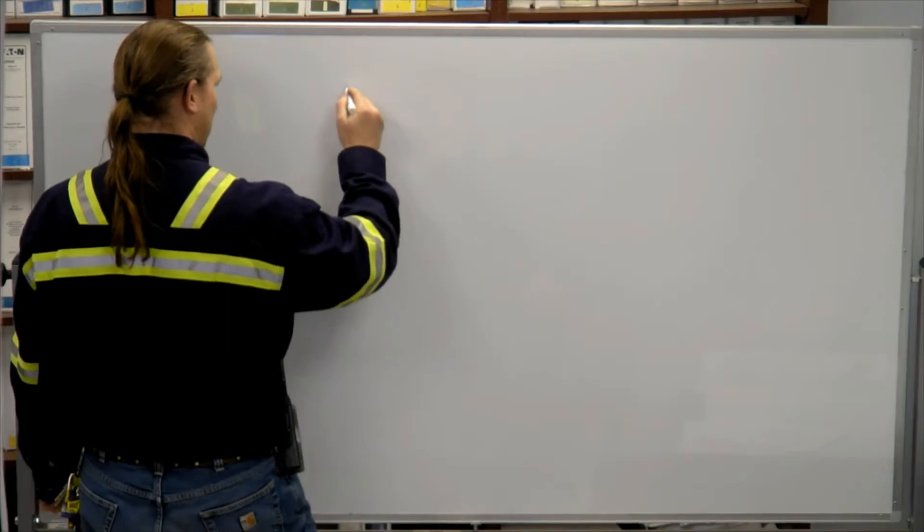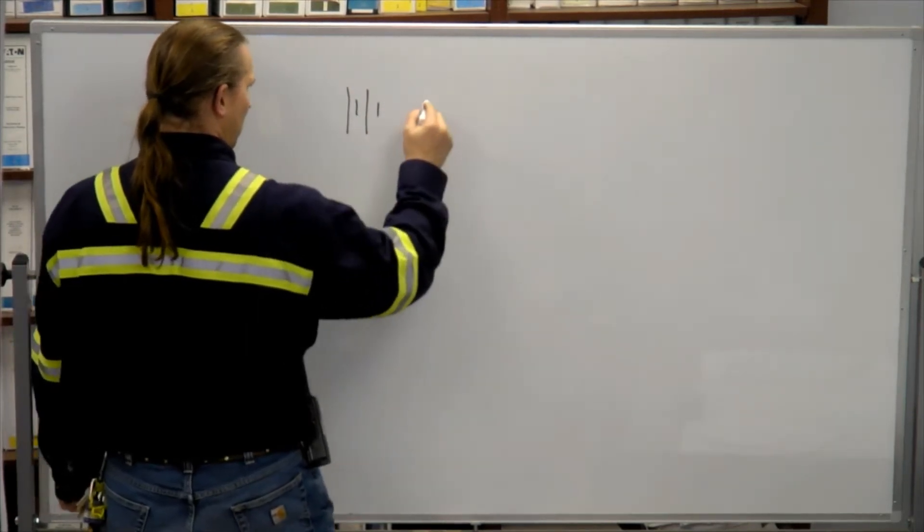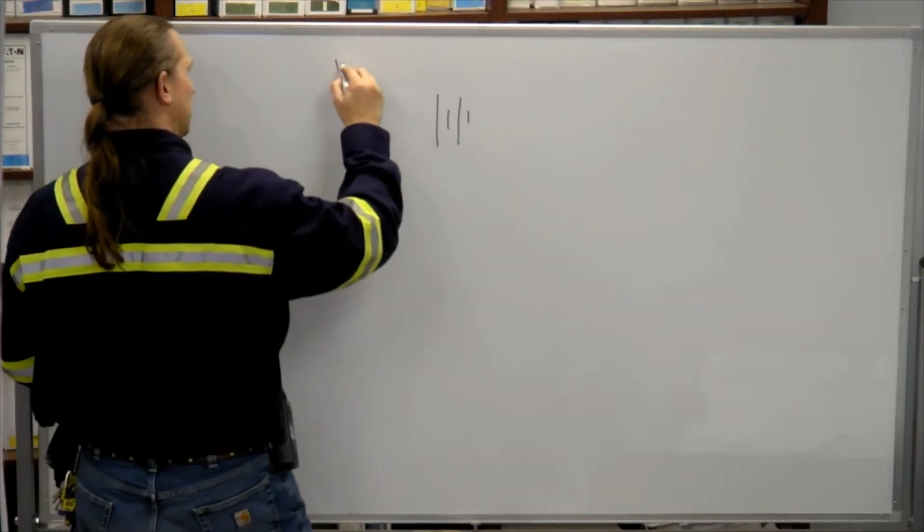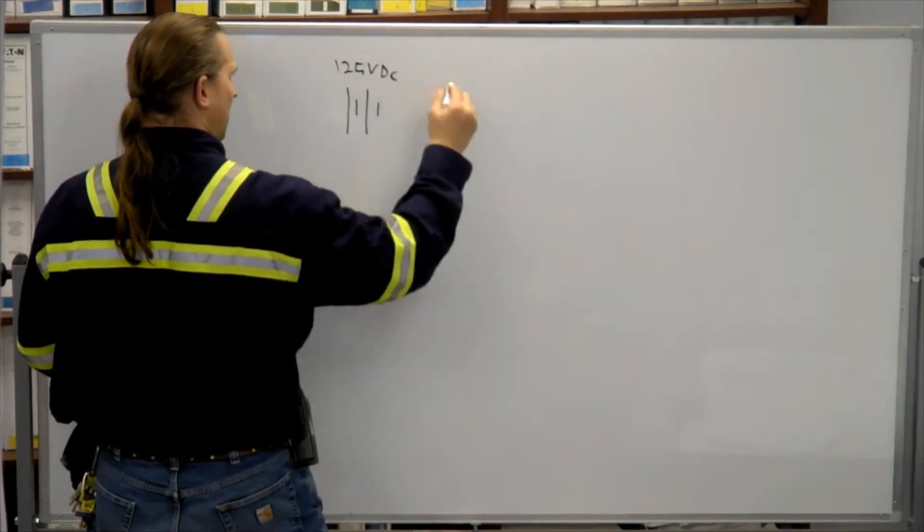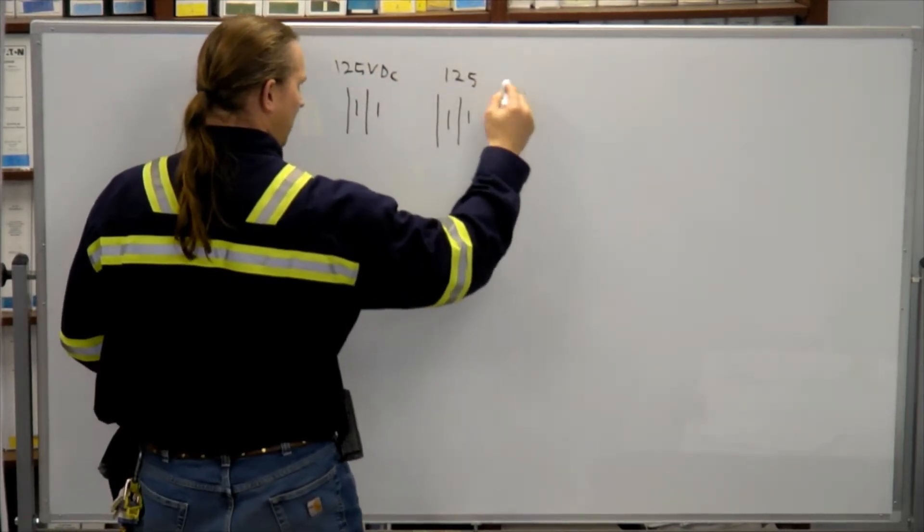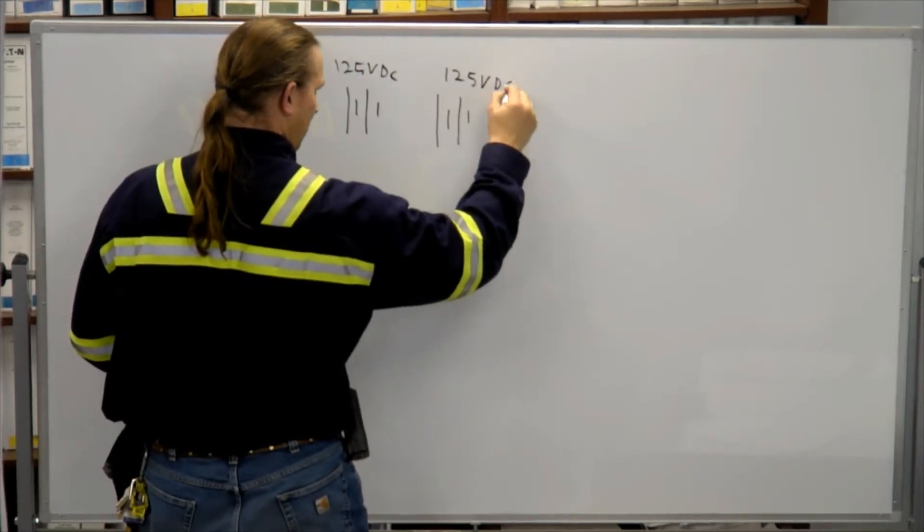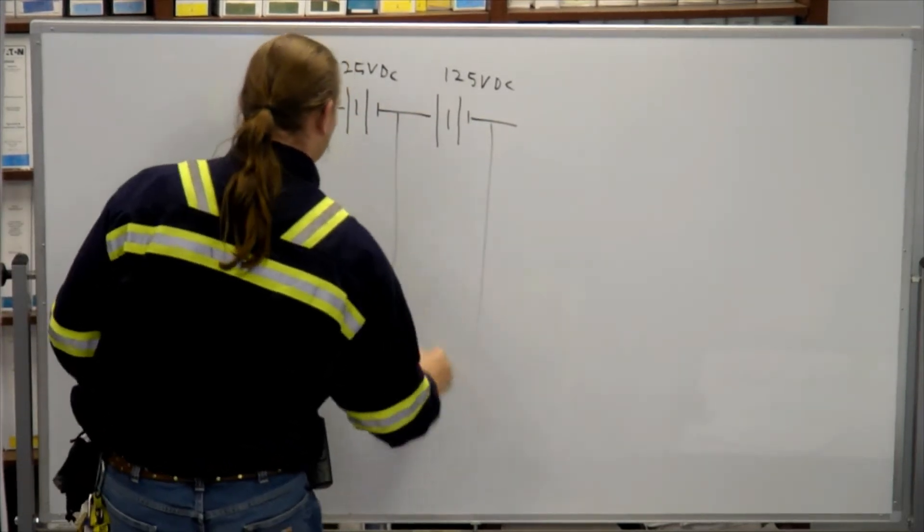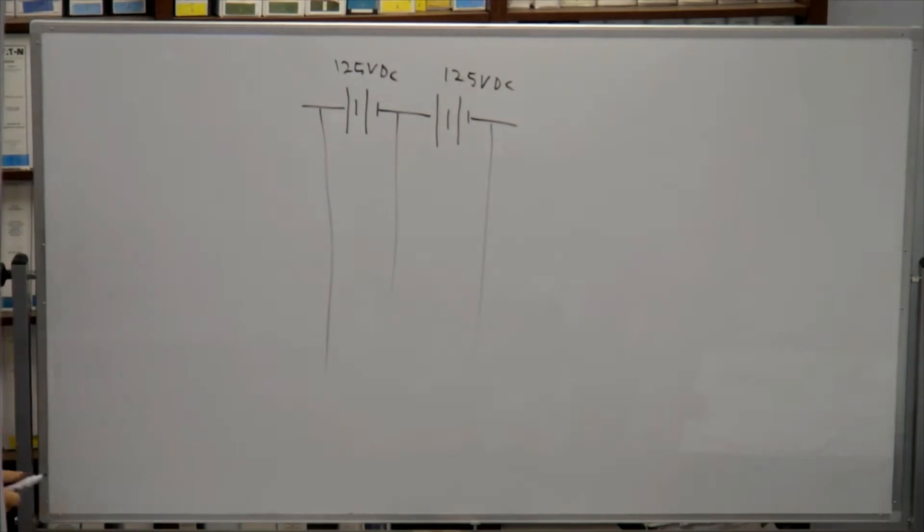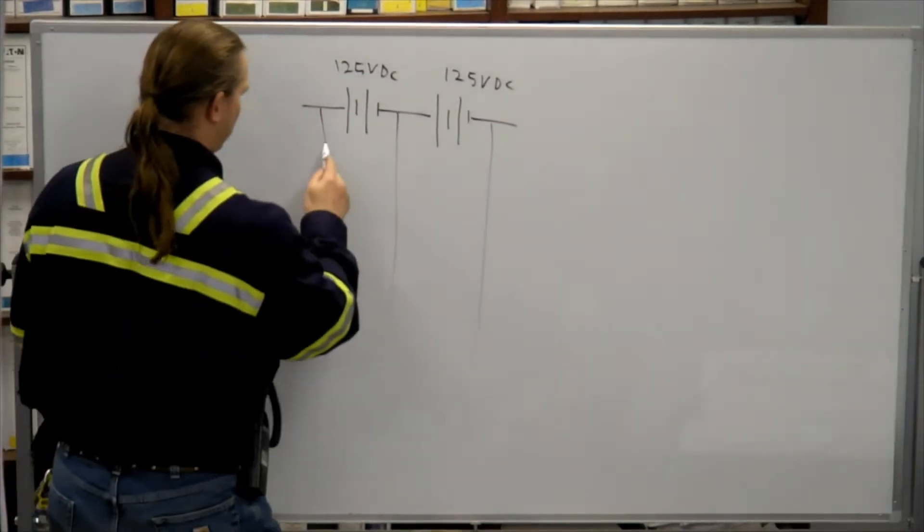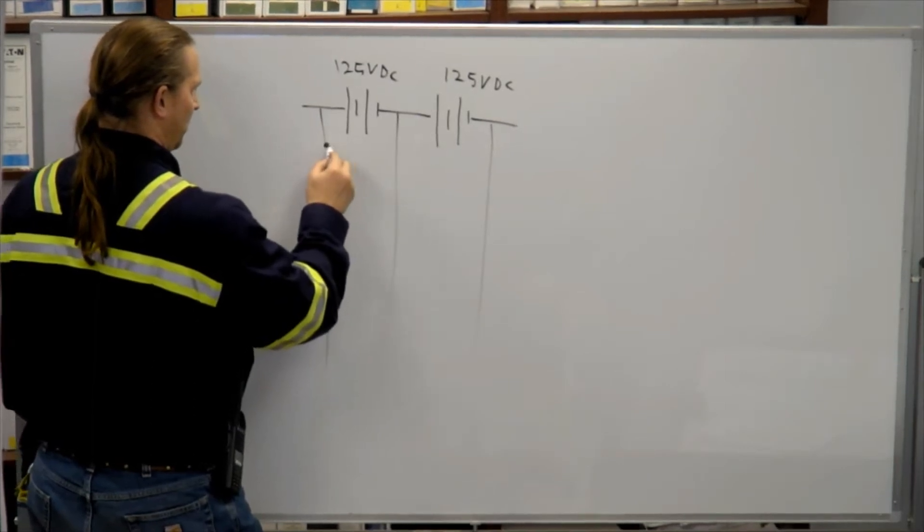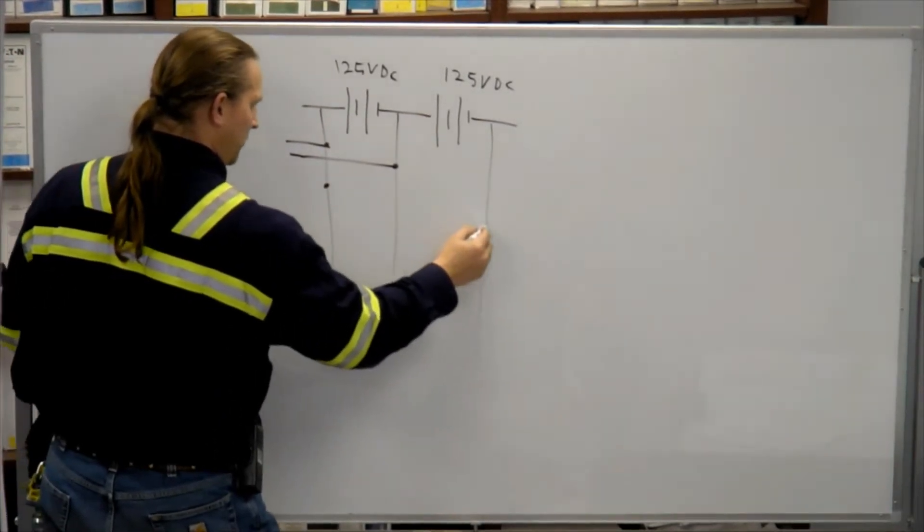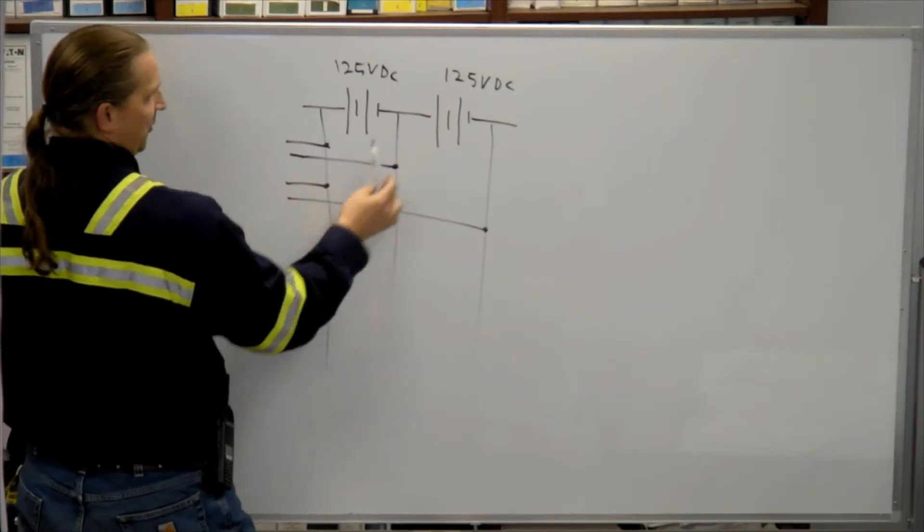So battery. We've got two battery banks that are both 125 volts DC. And then we have a switchboard coming off of those, and some loads tap across just half of it and other loads tap across both and use 250.